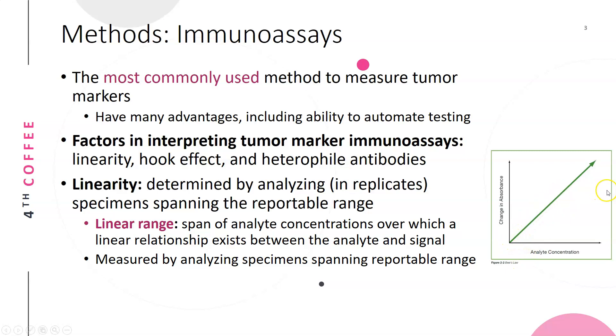You want the concentration-signal relationship to be a straight line. If it starts deviating — flattening out — then you have lost linearity. You can only report concentrations from the lowest to the highest concentration where the relationship remains linear and predictable. Linearity is determined by analyzing specimens that span the reportable range, from very low to very high concentration.